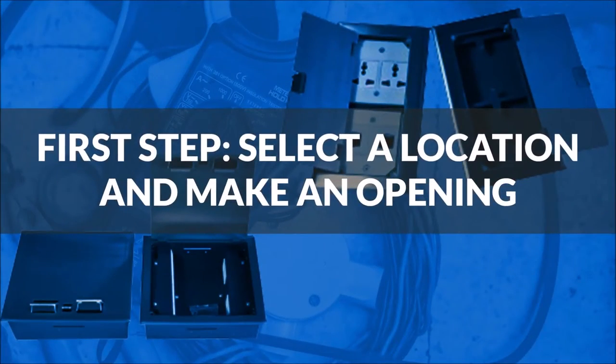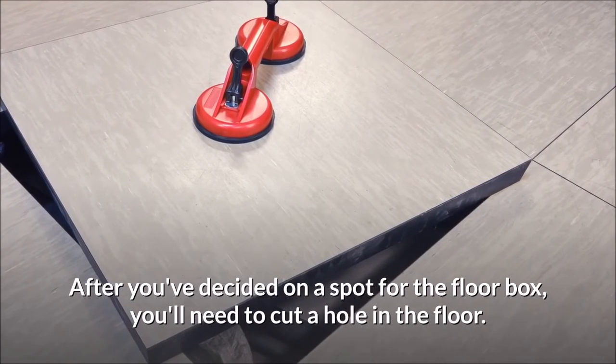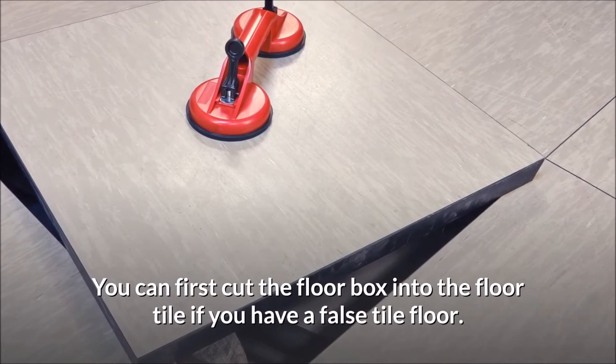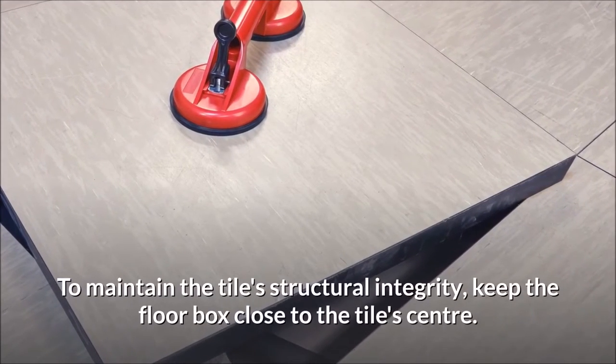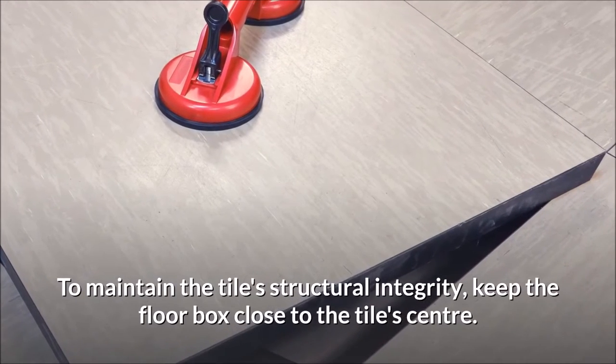First step, select a location and make an opening. After you've decided on a spot for the floor box, you'll need to cut a hole in the floor. You can first cut the floor box into the floor tile if you have a false tile floor. To maintain the tile's structural integrity, keep the floor box close to the tile's center.